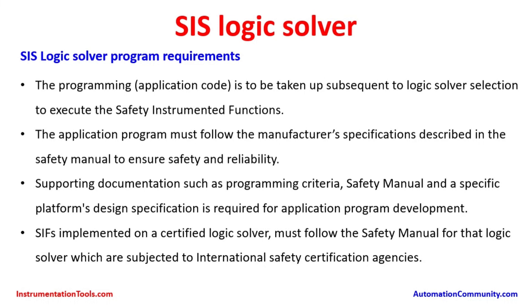Each manufacturer of logic solvers or processors will go through an approval process from international agencies like IEC, Exida, and TÜV. Based on their approval only, they can deliver products with the required software, and for that they have to develop a safety manual as well. Those best practices must be followed. Supporting documentation such as programming criteria, safety manual, and specific platform design specifications are required for application program development.